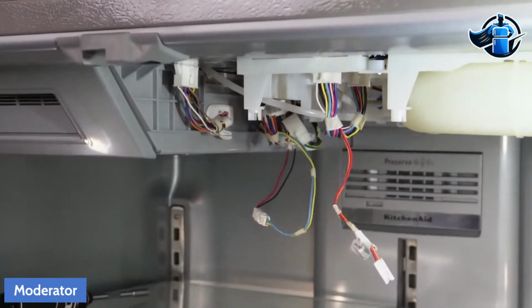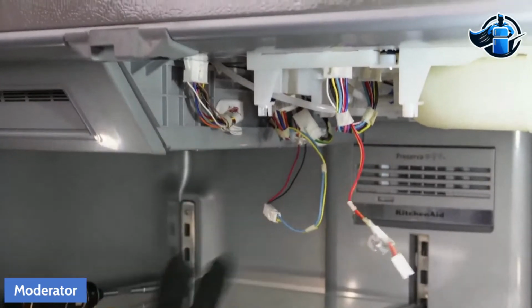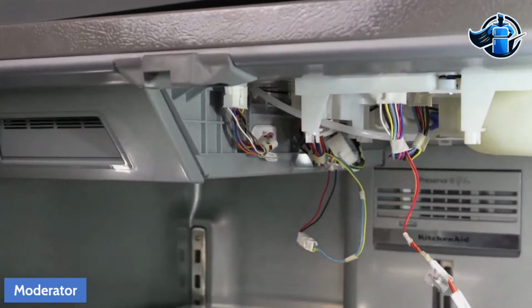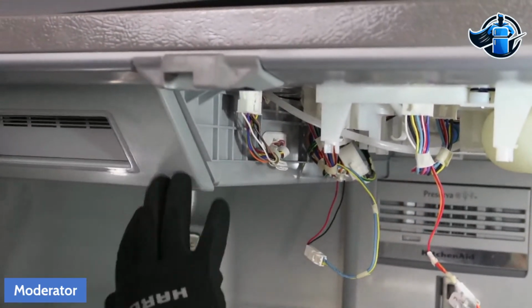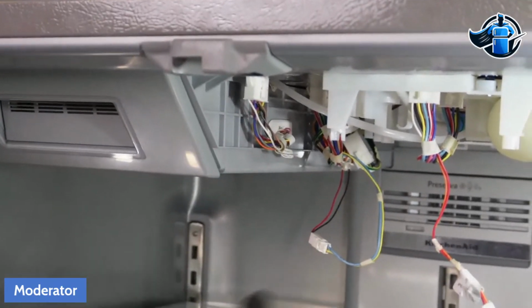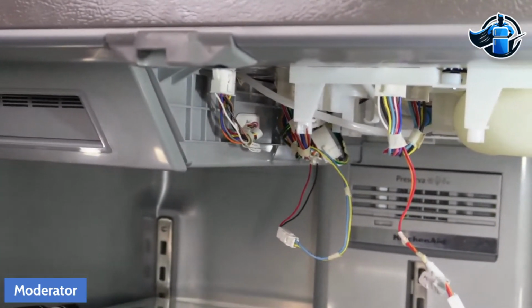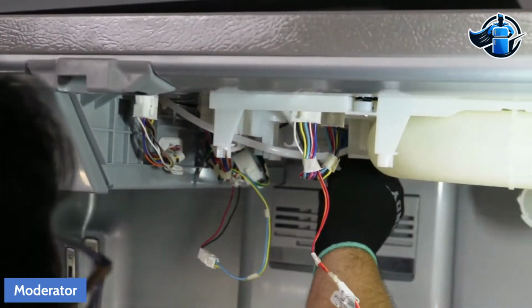I just replaced this fill tube heater. Always check voltage. Make sure you're getting voltage to the fill tube heater. Check your model. Some of them will have a 120 volt fill tube heater. Some of them are low voltage, DC voltage.